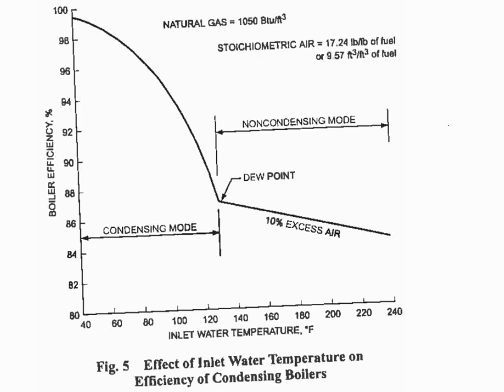So if you look at the efficiency of boilers in general, right, it depends on what temperature water you're working with. So down in the bottom of this chart, we go from 40 to 240 degrees of inlet water temperature to the boiler. That's my return water temp. Up the left-hand side, I've got 80 to 100% boiler efficiency. So when I take a typical 180-degree supply system with typical 20-degree delta T on the radiators, that means I've got 160 coming back as my return. This particular boiler we're looking at is an 86% efficient boiler. This is just a generic boiler out of the ASHRAE handbook, but you get the idea.